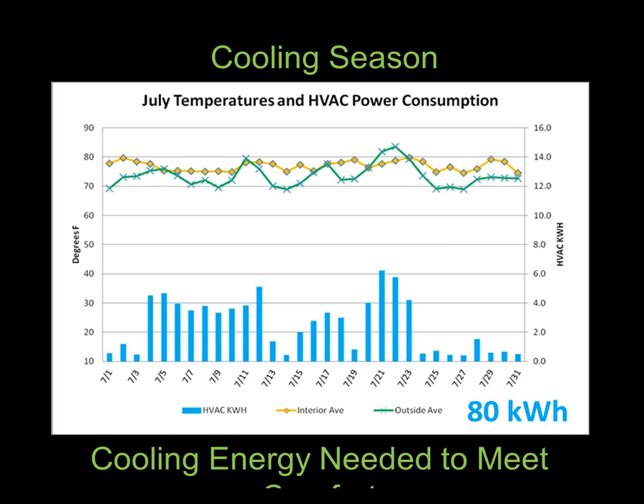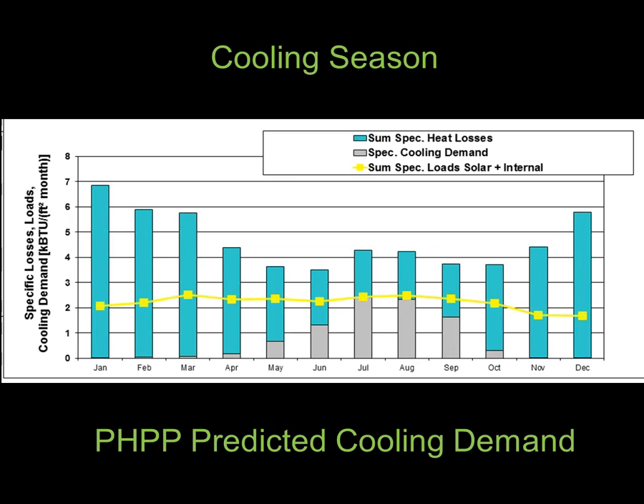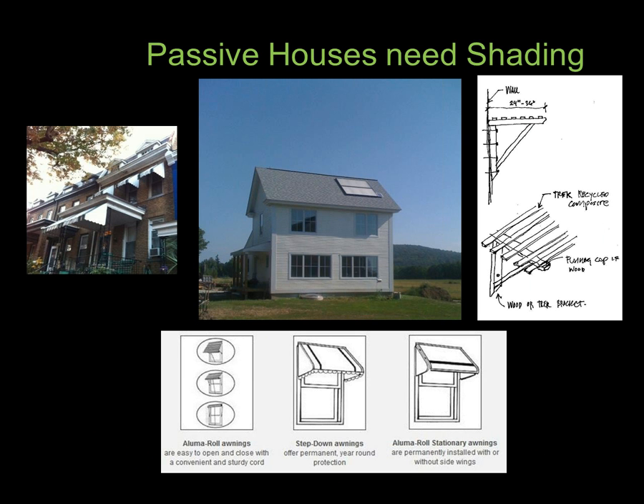Cooling. Now, this is something that I want to touch on here because I think it's an important part. We definitely saw some warmer temperatures than one may have wanted, and the heat pump turned on for cooling. And you can see the PHPP more or less predicted that we were going to have a cooling demand in the summer. So shading is critical in a passive house, and we did not have it on the lower southern side windows, and you could really see that in the temperatures inside. So there are plans for a trellis to be built before we get into the warmer parts of the summer, and hopefully that will help keep a lot of that unwanted passive solar gain in the summer out of the building.